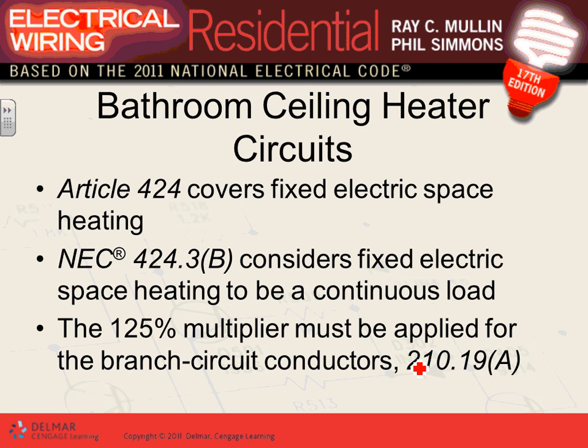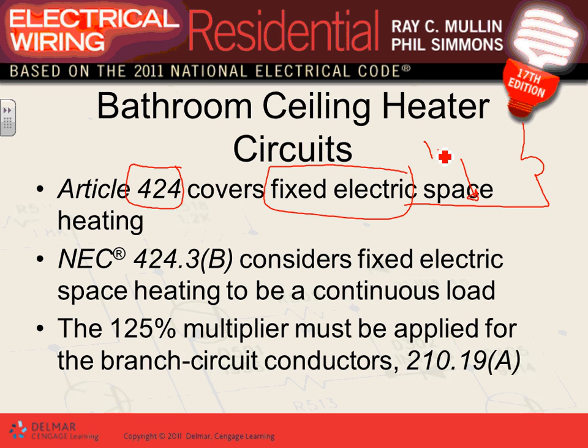Bathroom ceiling. If you have a heater, like a baseboard heater, the article that talks about heat is Article 424. If you have a fixed electric heater, here's how we're going to do it. Very simple. When you size your conductor, 1.25 times full load current. When you size the overcurrent device, same thing, 1.25 times full load current. Done. For example, if you have a 10 amp heater, like the baseboard heater you guys did, and you need to size a conductor for it, what do you need? Take the 10 amps, multiply it by 1.25, and you get 12 and a half.